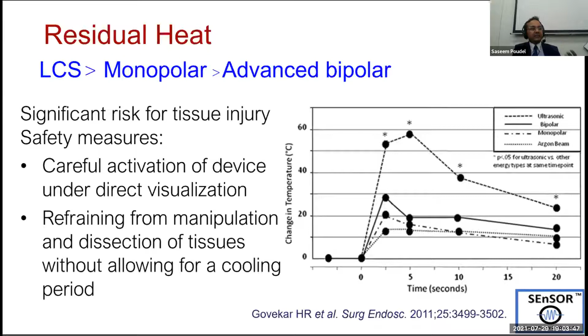The safety measure is you need to carefully activate the device under direct visualization. Make sure that you see where the active electrode is all the time when you're activating, and do not manipulate or dissect the tissue without allowing the active blade to cool. Dr. Sujit has some videos showing the residual heat and lateral spread. I'm going to stop sharing my screen. Okay, so Dr. Sujit.